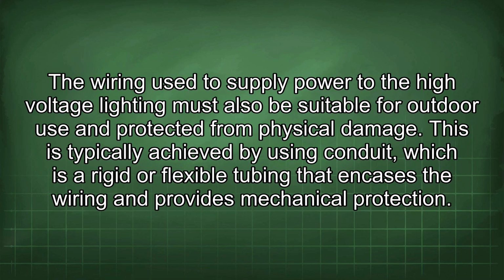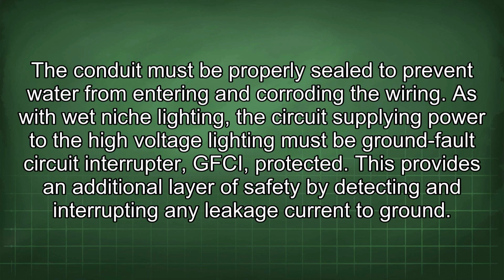The wiring used to supply power to the high-voltage lighting must also be suitable for outdoor use and protected from physical damage. This is typically achieved by using conduit, which is a rigid or flexible tubing that encases the wiring and provides mechanical protection. The conduit must be properly sealed to prevent water from entering and corroding the wiring. As with wet niche lighting, the circuit supplying power to the high-voltage lighting must be ground fault circuit interrupter (GFCI) protected. This provides an additional layer of safety by detecting and interrupting any leakage current to ground.